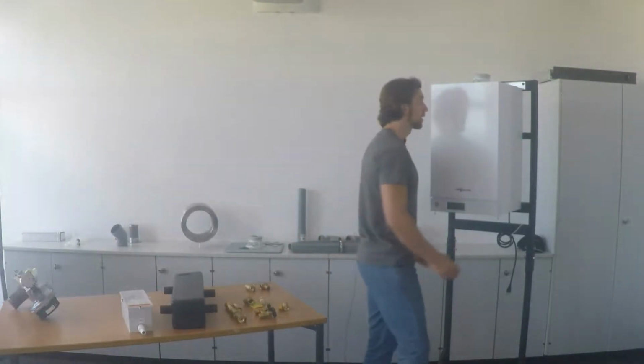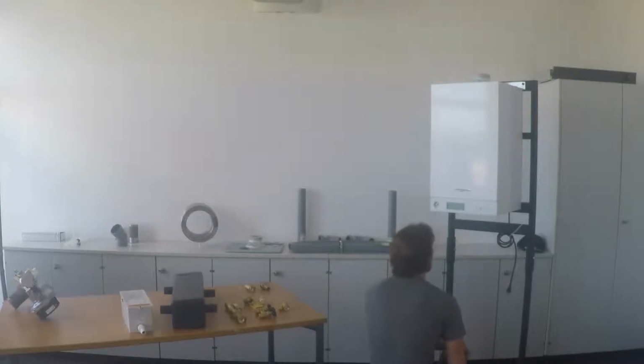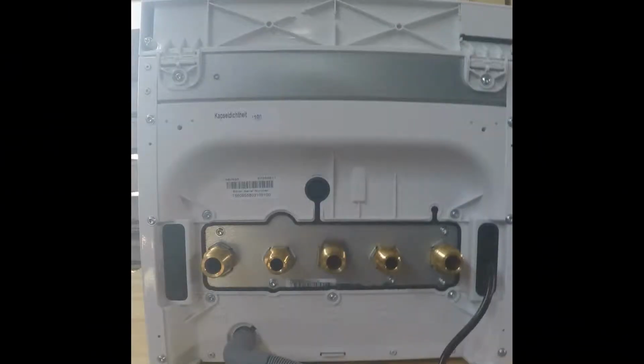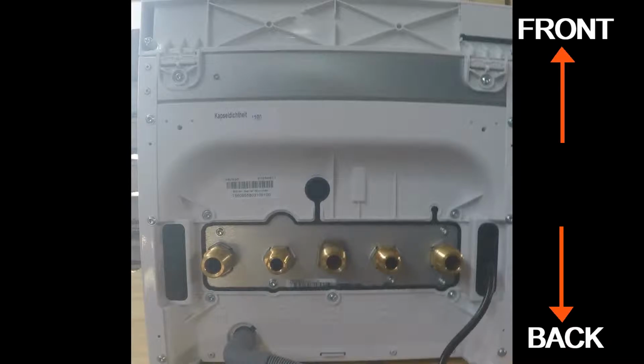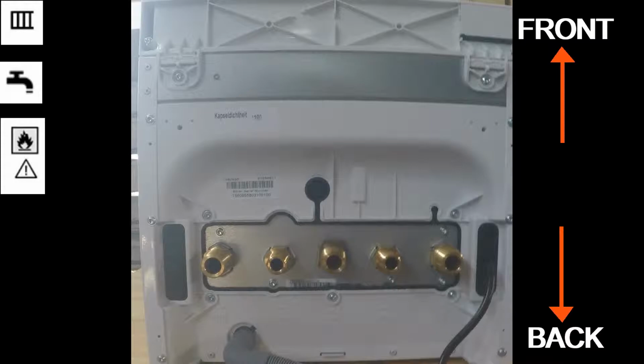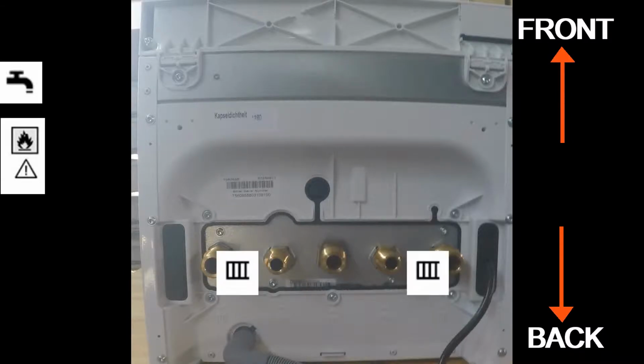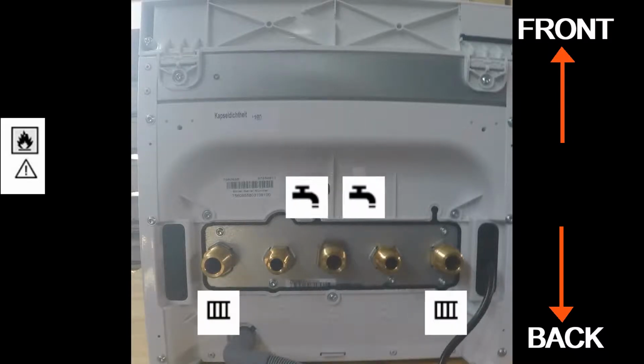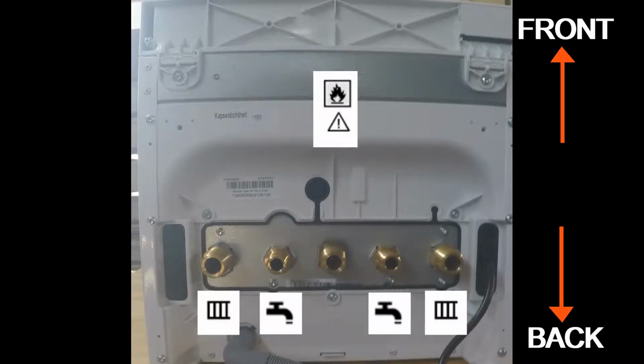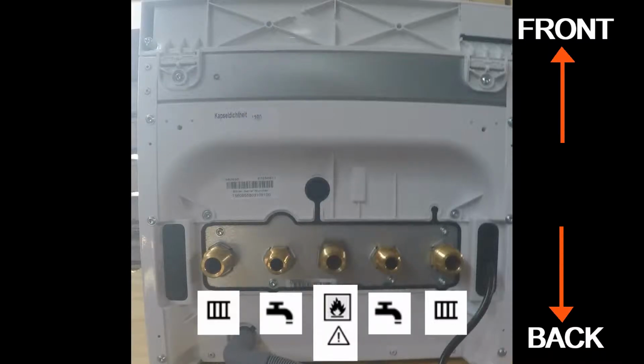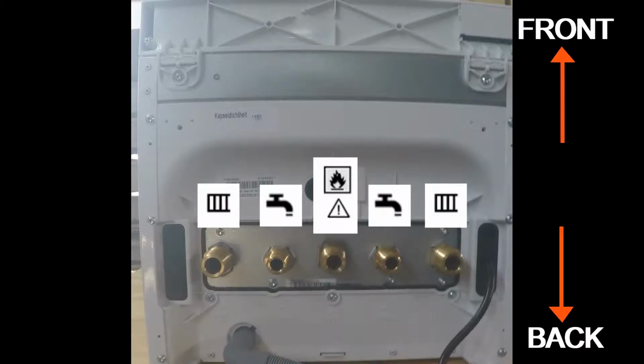Let's take a look at where they actually go on the boiler. So if you face the boiler like I am right now, and you take a look underneath, this is what you're going to see. Regardless of whether it is a B1HA or a B1KA, you will see these symbols behind the connections. Those symbols stand for supply and return heating, domestic hot water, and your gas. Next to those symbols, you should also see arrows that point towards or away from the fittings. This means that the flow is either into or out of the boiler.